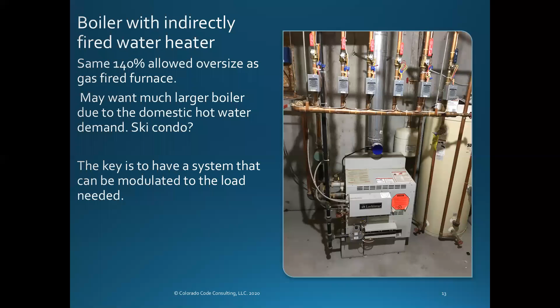I didn't see that. What it says is that we can only size the heating system 40% larger. Well, you can do that, but you may have to have a modulating boiler to do it, or more than one. A lot of times there's 3 or 4 of these boilers, and they all crank up when they're having hot water. So it's not like you can't do it, but that's how you'd have to do it.